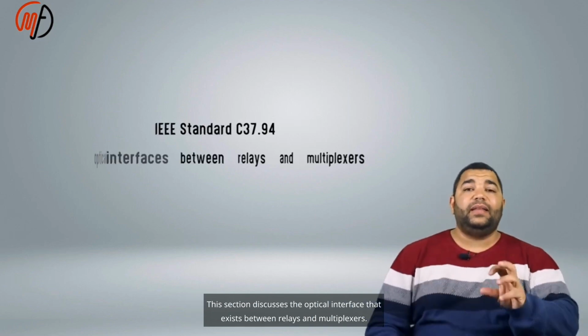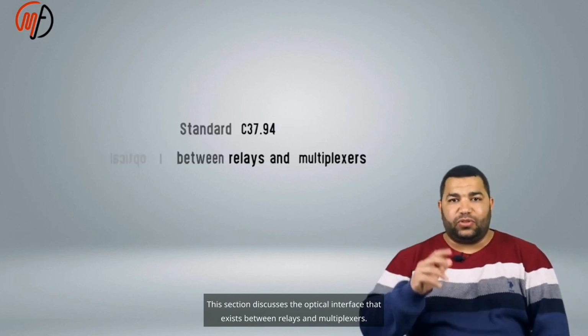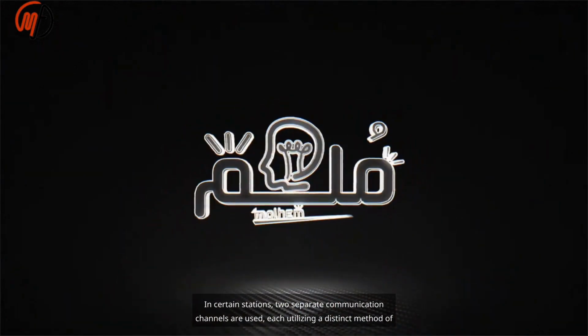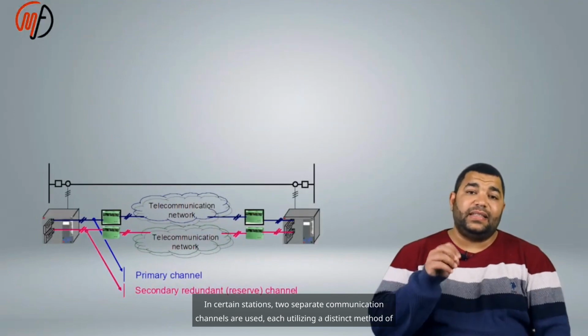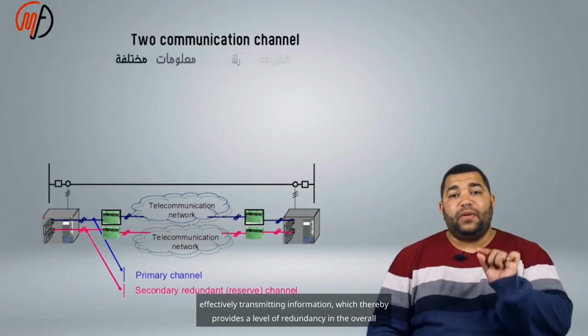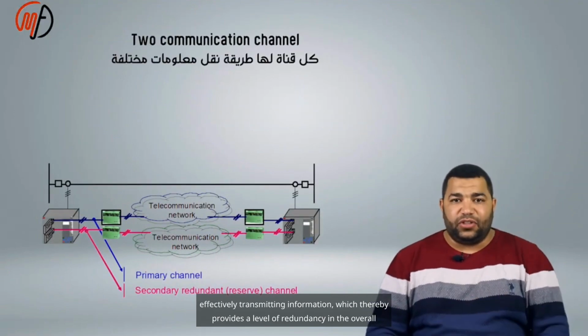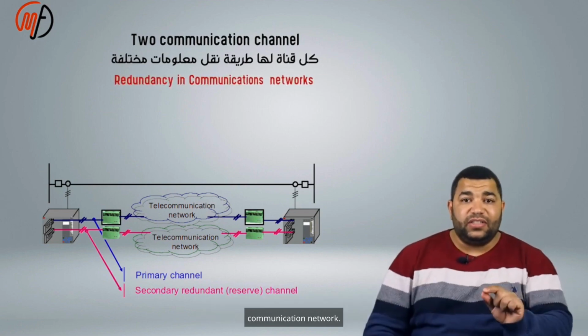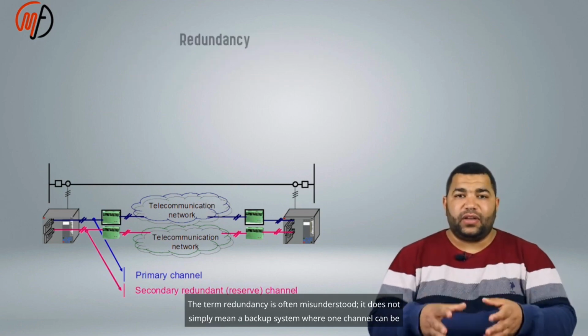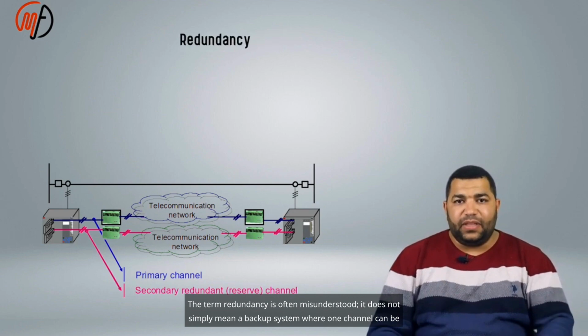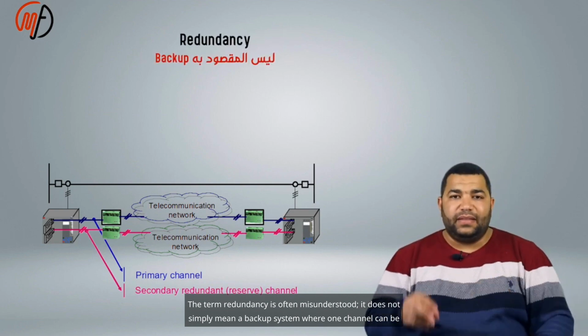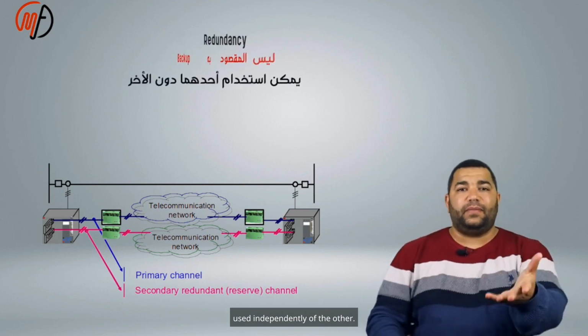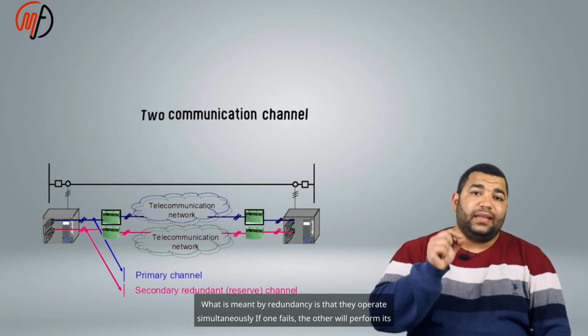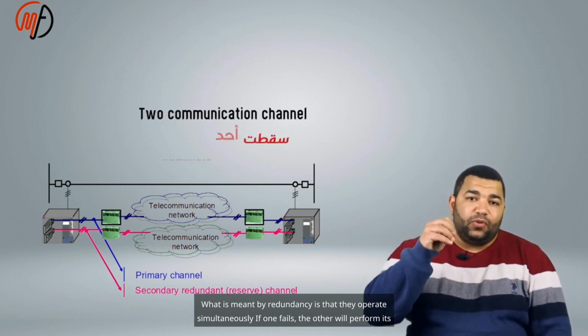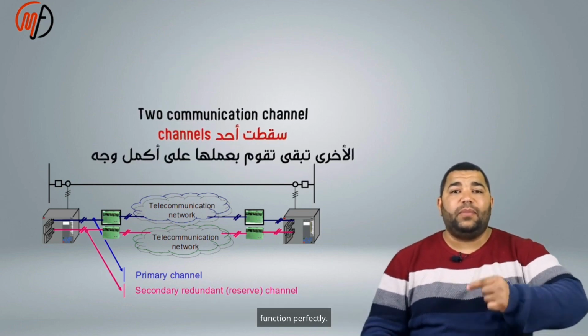This section discusses the optical interface that exists between relays and multiplexers. In certain stations, two separate communication channels are used, each utilizing a distinct method of effectively transmitting information, which thereby provides a level of redundancy in the overall communication network. The term redundancy is often misunderstood. It does not simply mean a backup system where one channel can be used independently of the other. What is meant by redundancy is that they operate simultaneously. If one fails, the other will perform its function perfectly.